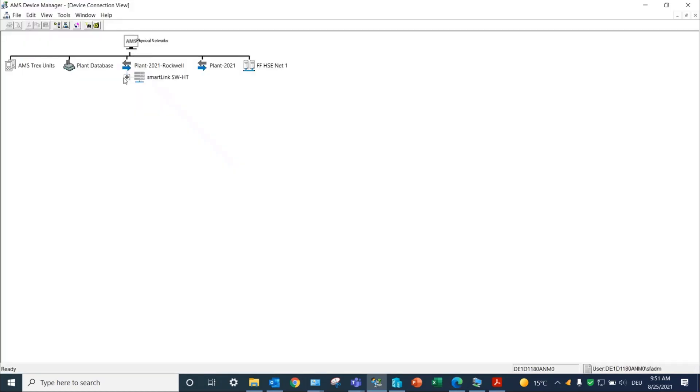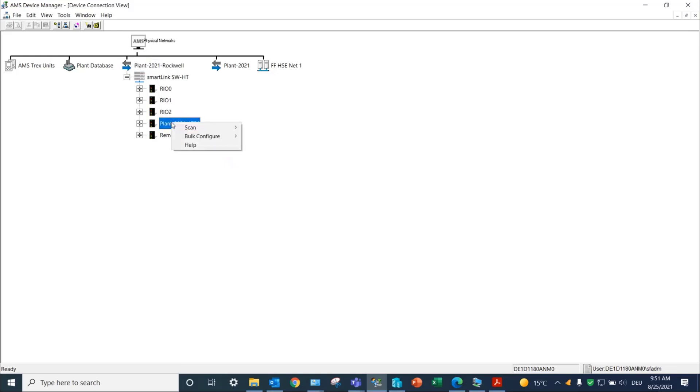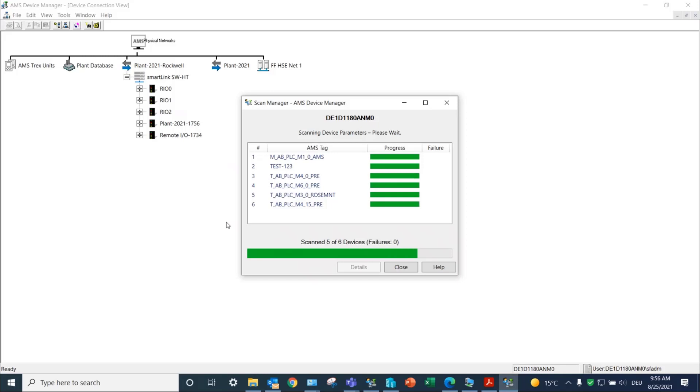Notice the previously configured Allen Bradley and Schneider Electric PLCs are now displayed in AMS Device Manager. Click on Scan all devices to retrieve the parameters of HART field devices. In our test, six devices have been discovered under the 1756 PLC.